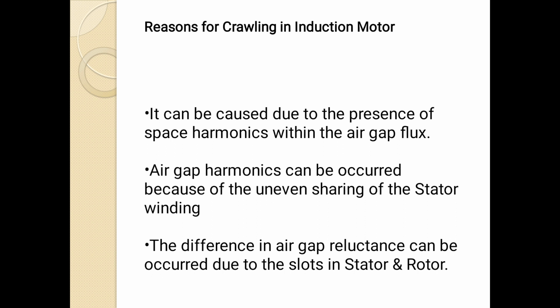Reason for crawling of induction motor. It can be caused by the presence of space harmonics in the air gap flux. Next, air gap harmonics can occur because of uneven spacing of the stator winding. The difference in air gap reluctance can occur due to the slots in the stator and rotor.